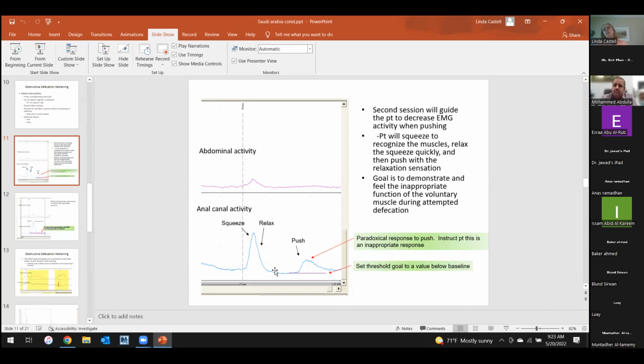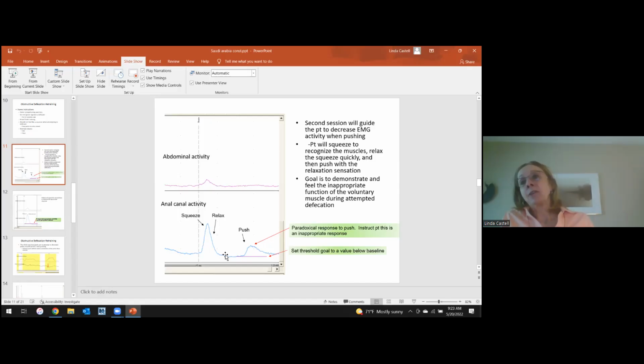100% with you there. And this London classification or protocol is also suggesting that once you position your catheter in the anal canal, wait 3 whole minutes before you do your resting pressure, because that will allow the catheter to warm up and you don't have the drifting. Also the patient has accommodated the catheter, and you don't have spontaneous activity. But I think you're right.